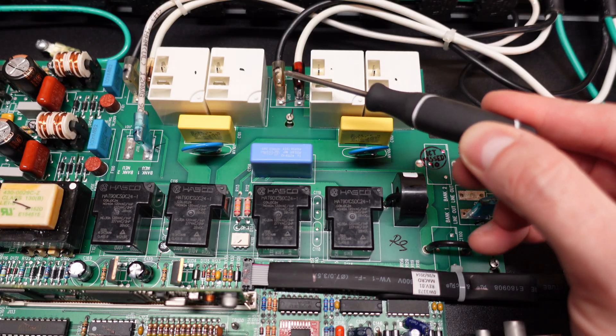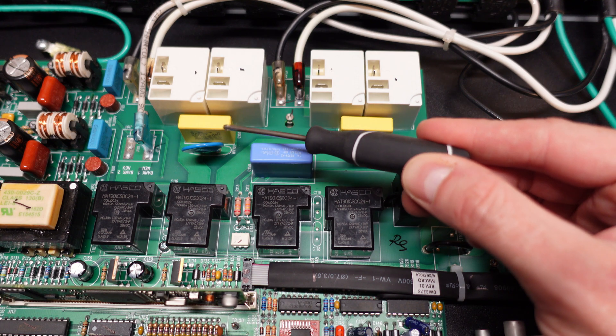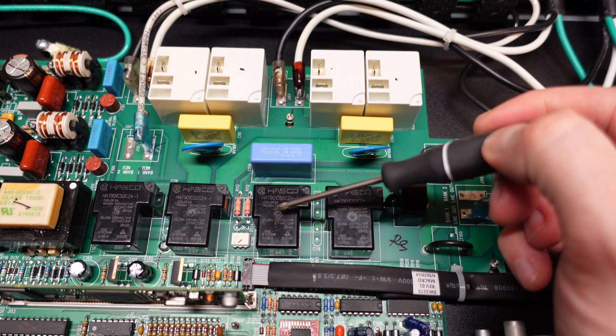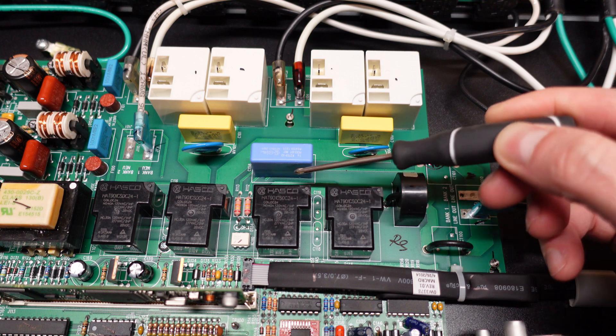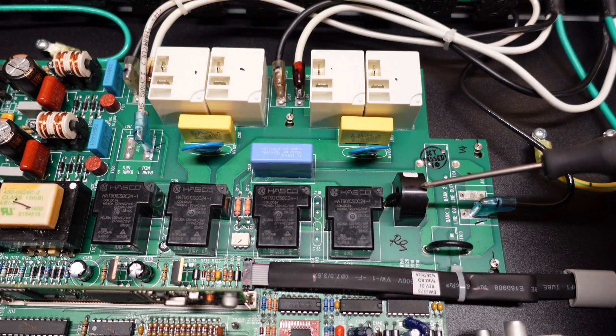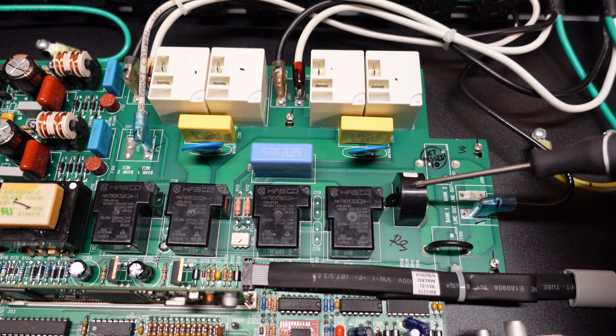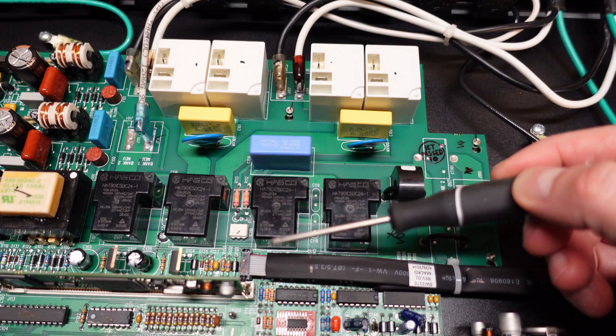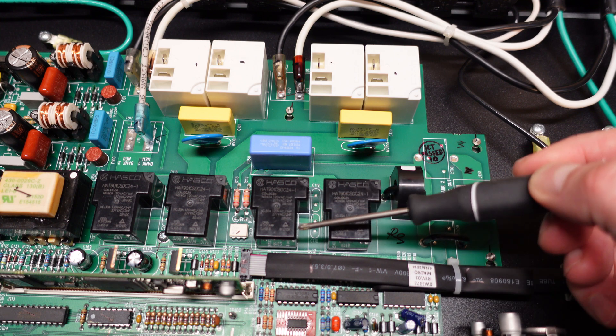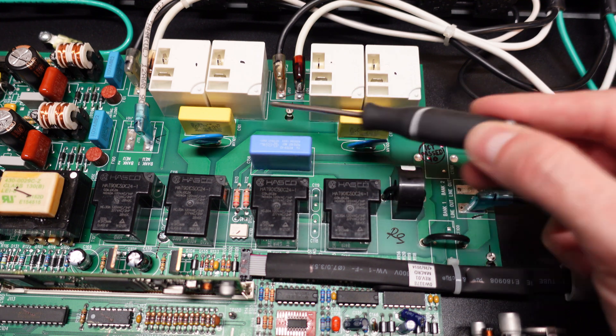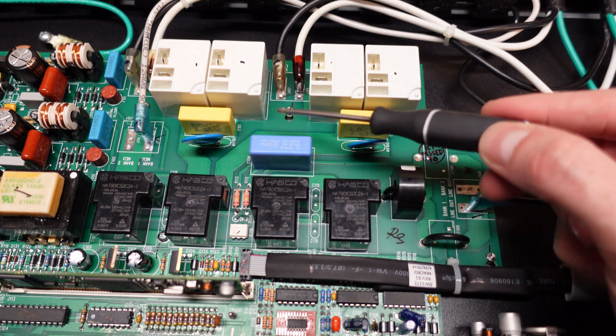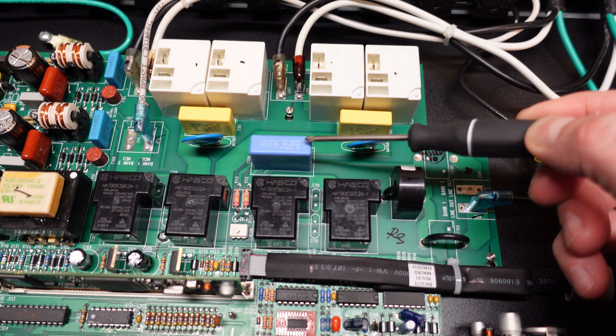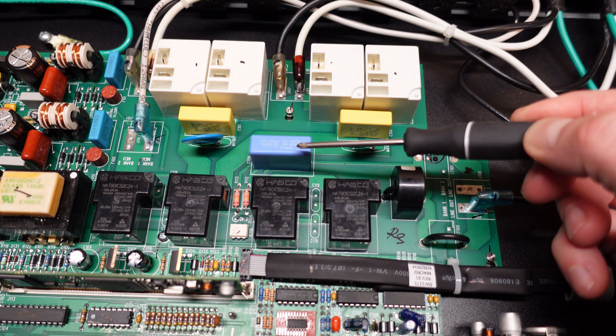Both of these are the line switching relays. We can't exactly see the traces. They come out to this yellow capacitor and then stop. However, I do believe they're both going into this relay on the underside of the circuit board, similar to what we see over here, then being passed to this relay, which you can see the run here. The output of this relay is going through - this is a current transformer, so this is what's metering the amount of current for the front reporting display - and then that's going over here to the output hot lead. So there would be a bit of interruptive time with these switching of relays. However, I do notice that they have capacitors both on each input, and then they have what appears to be a combined capacitor here. So I don't know if these capacitors are smoothing out that voltage and smoothing out that difference in phase between the two sources. That's how I believe it's working.